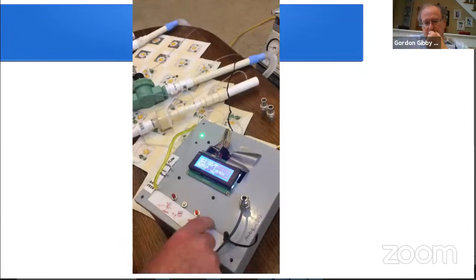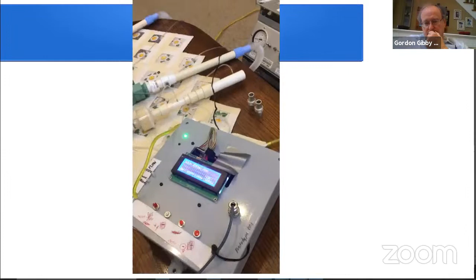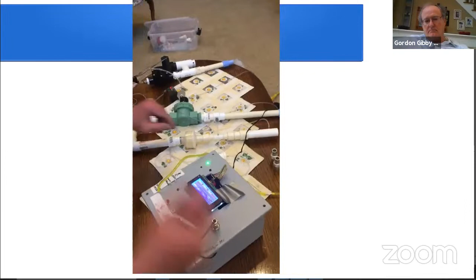When we go to the adaptive controller, things are not quite so spiffy. Gotta go down and go to the adaptive controller. Select, and then go out of here. And okay, now it's on an adaptive controller, and it has to pick the exact one moment in time to close this valve again to keep pressure in the system. It opens everything to let the patient exhale, and it closes it before the patient can completely exhale, trying to keep a pressure. It's set to hit 10, but it's only hitting 5.